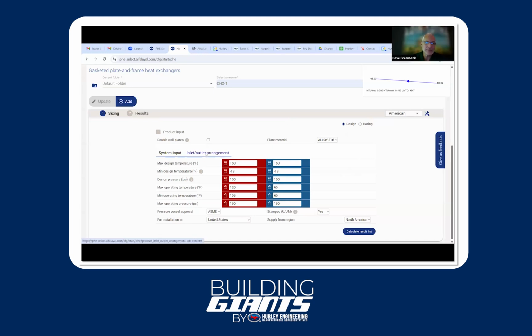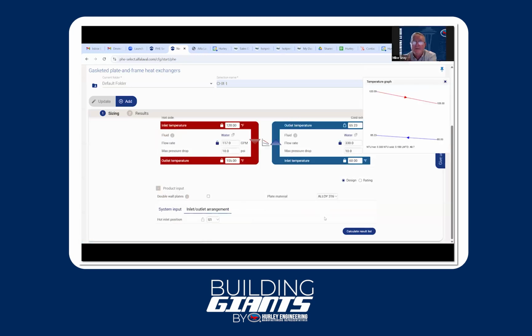You can also click down here on your inlet/outlet arrangements where you can change where the hot inlet would be, and it will change the configuration of the front portion of your plate pack, and also the arrangement of the plates. So S1 is typically the inlet on the hot side. If you need to change that because of your configuration, we've had to do that on some data centers and stuff like that to meet the criteria to hook the system up. Just know that's available for you.